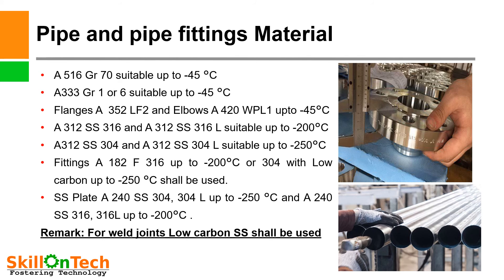Pipe and pipe fitting materials. Generally in industries, pipe and pipe fitting materials are used for low temperature service where temperatures are –45°C, –200°C, or –250°C. The suitable materials are given in this slide: A516 grade 70 carbon steel plate is suitable up to –45°C; A333 grade 1 or grade 6 pipe is suitable up to –45°C. A picture of a pipe and a picture of a flange are also shown. Flanges A350 LF2 and elbows A420 WPL1 grade shall be used.